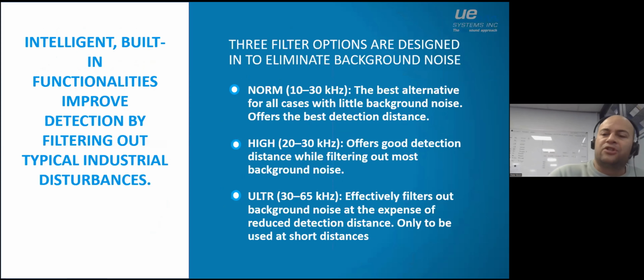The same as with leak detection, the plus version of the camera that does leak detection and electrical also has 3 different filters. We did that because you never know what the surrounding situation is. Is it a substation where it's very quiet? Then you can use a lower frequency filter. But if you're in a factory with a transformer and a lot of competing ultrasound, maybe you use the ultra filter so it only picks up the higher frequency sounds.